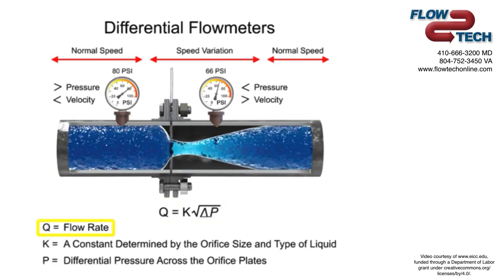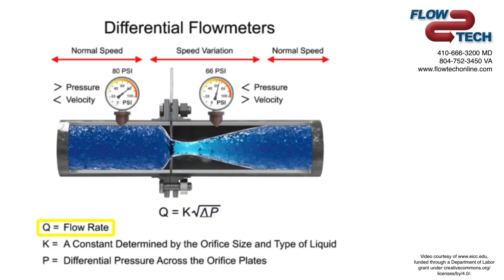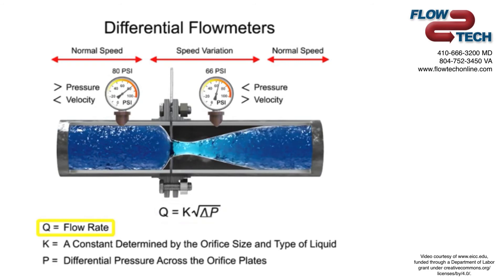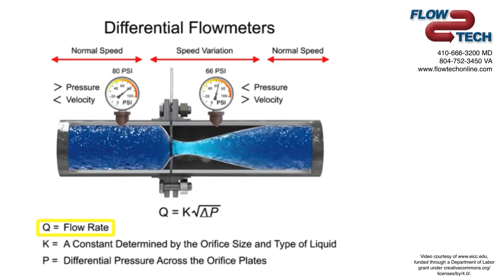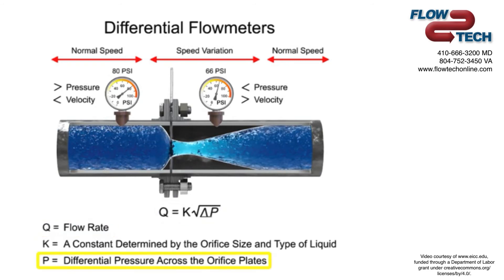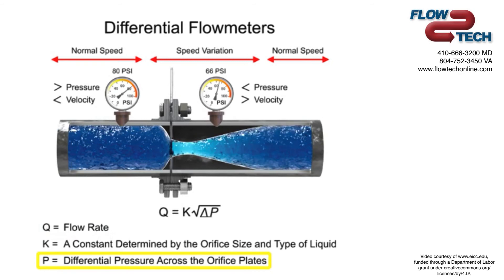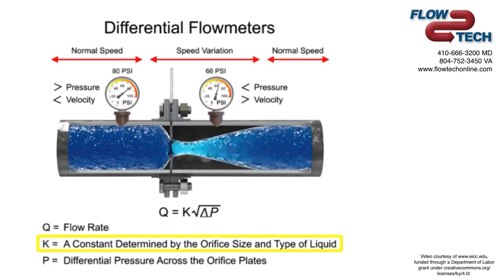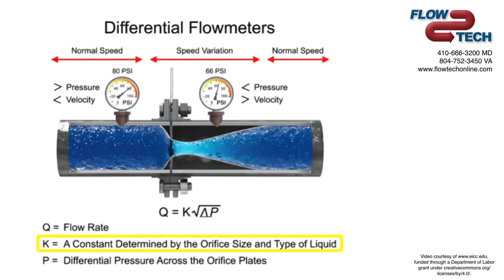The flow rate, Q, of a fluid through an orifice plate increases in proportion to the square root of the pressure difference on each side, multiplied by the K factor.